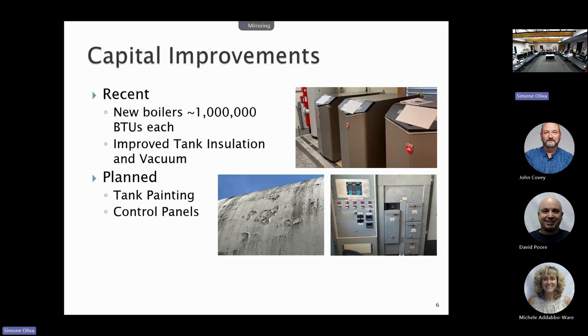The boilers are cascading and modulating, with a lead boiler and 2 follow boilers. They have internal technology where they remember the last run and can predetermine if they need to ramp up sooner or later depending on what we're putting into them. It's adaptive technology, constantly thinking for us. So you might see all 3 boilers running at 30%, which is the most efficient way for them to run, all within the boilers themselves.